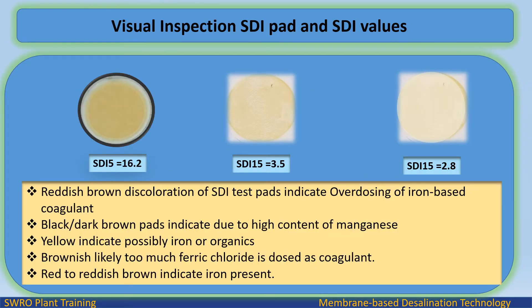SDI filter pad tests can be analyzed to determine the nature of the deposit. Visual inspection: reddish-brown discoloration of SDI test pads indicates overdosing of iron-based coagulant; black or dark brown pads indicate high content of manganese; yellow indicates possibly iron or organics; brownish likely indicates too much ferric chloride dosed as coagulant; red to reddish-brown indicates iron present.